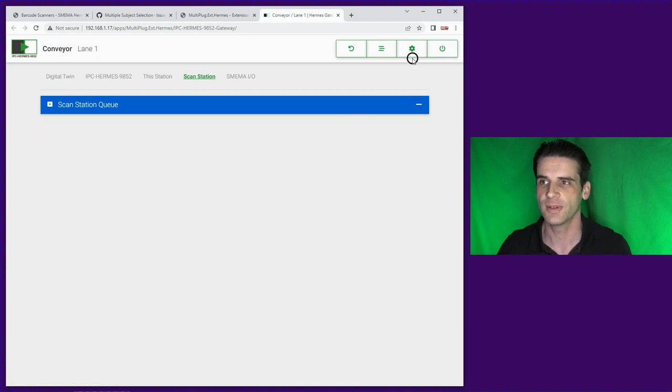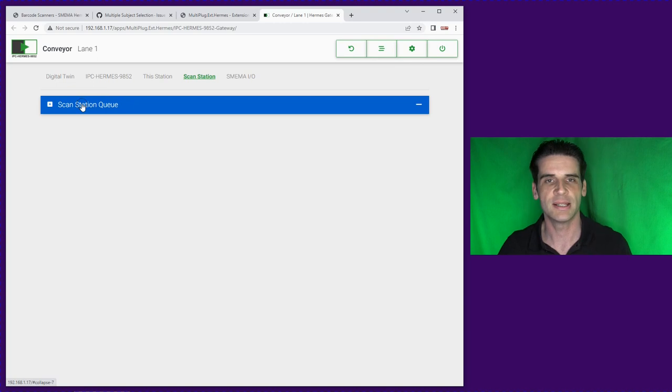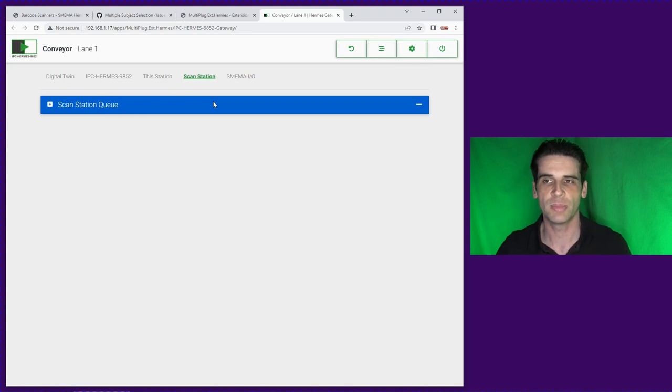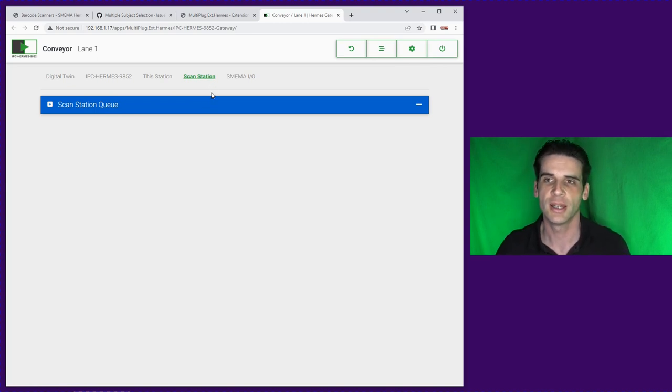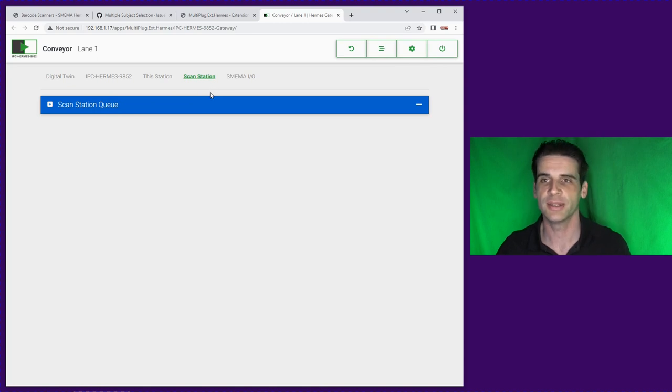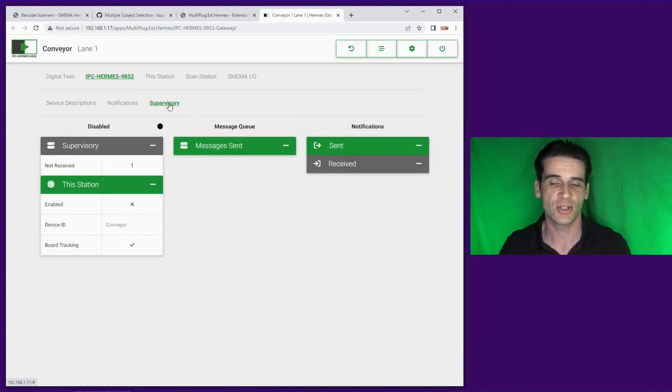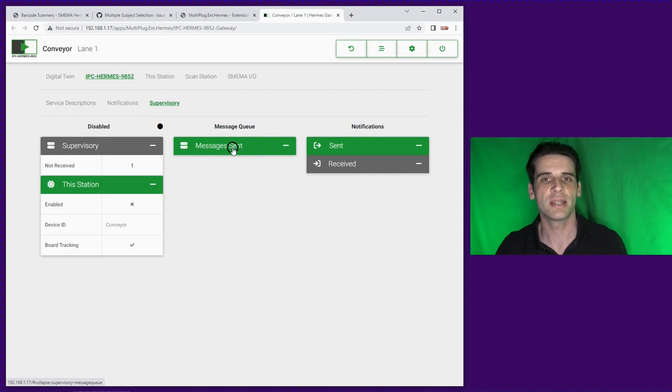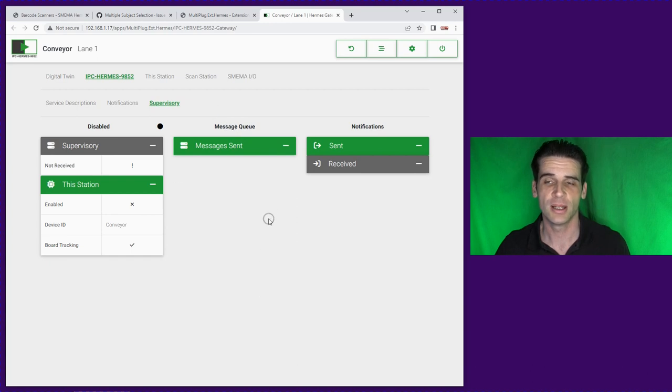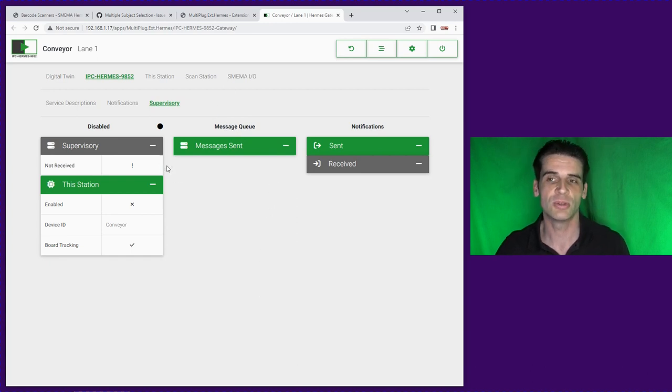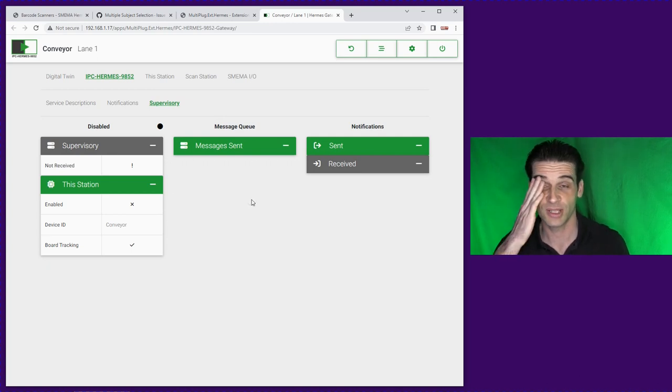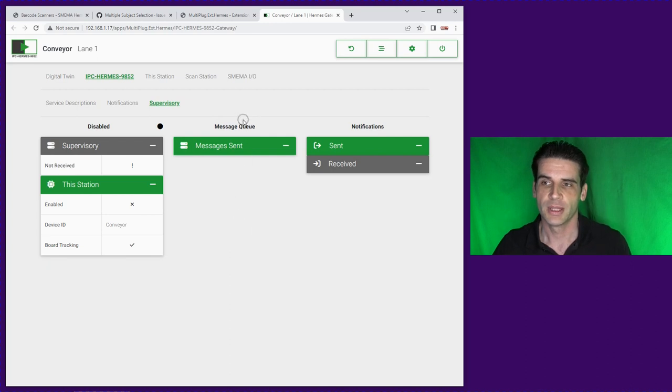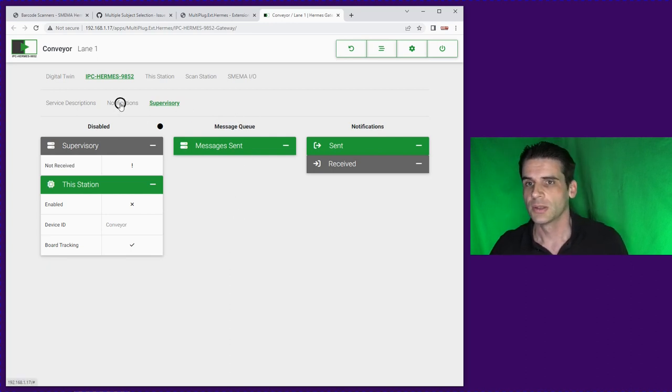And therefore once the machine gets that value it will stop and raise a warning to the operator and we can delete those as we see fit. The other state is an in-between state so it's not good not bad but it's not been replied to by the supervisory system. All the messages that have been sent by the supervisory system will be collected here so this queue should really always be blank because ideally the supervisory system has already replied to those messages.